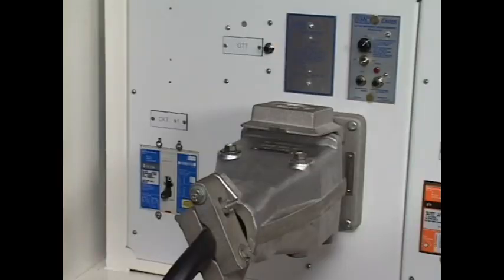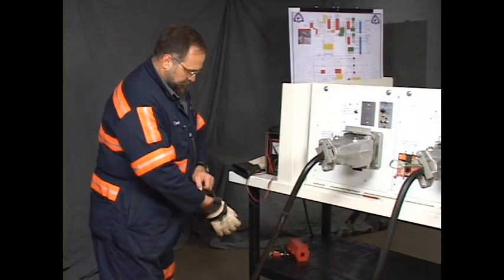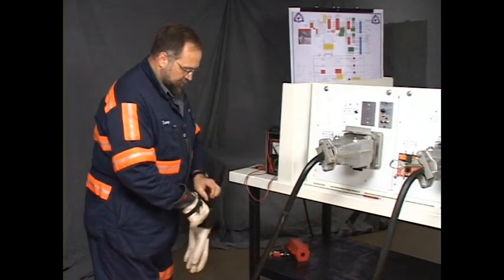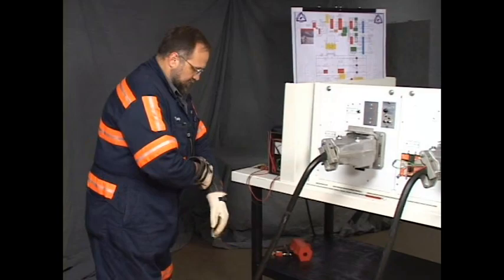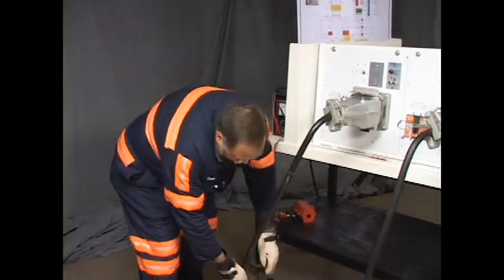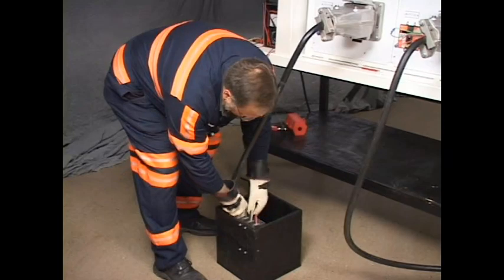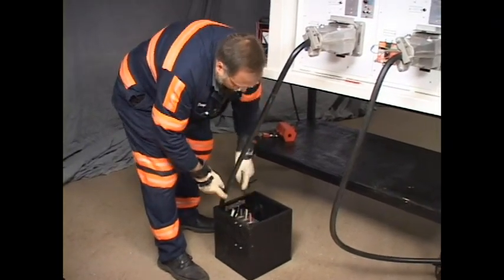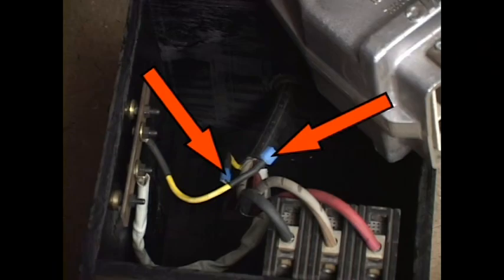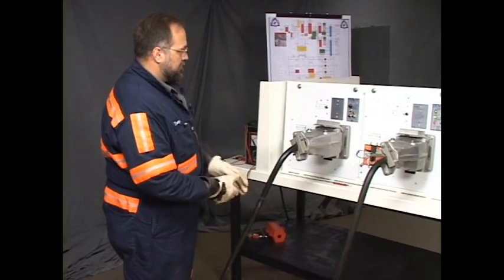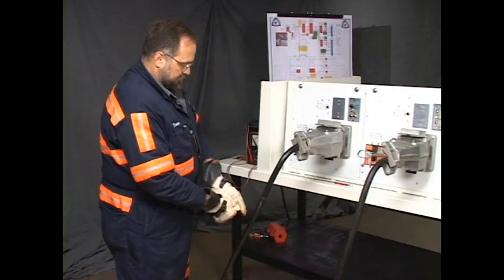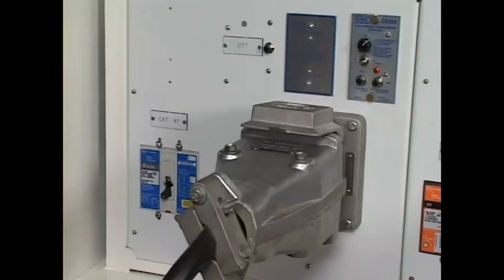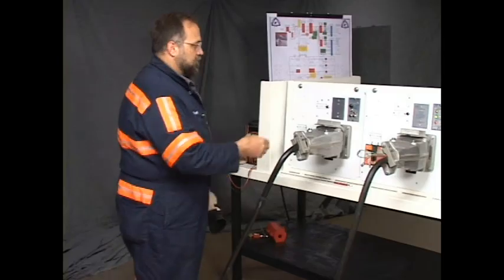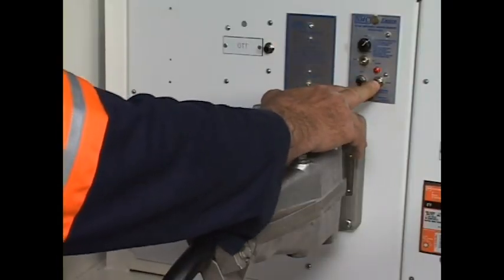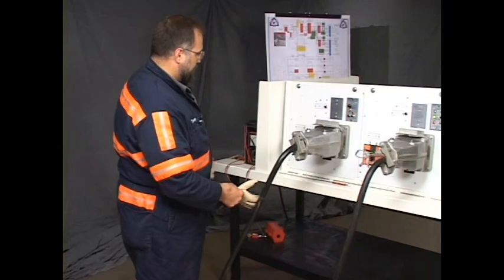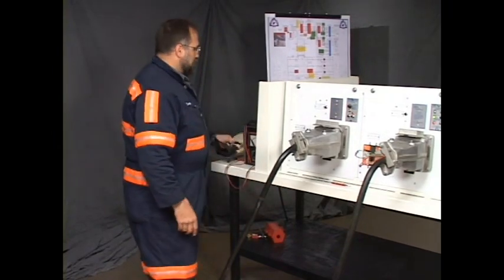Okay, I'm going to put my gloves on. Although the power portion of this box is not energized, I'm going to put my gloves on, and to simulate this problem, I'm going to open the ground monitor conductor at the machine. Now, as you can see, the red tripped light is now on. I'm going to operate the reset. To no avail, it doesn't work. So we have a problem. The monitor won't reset.